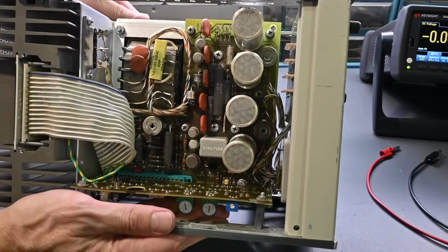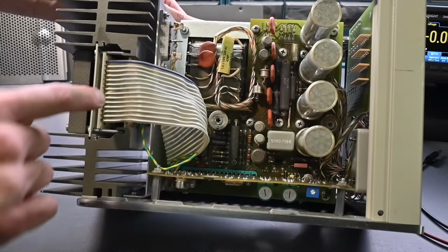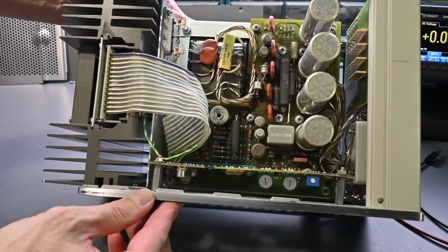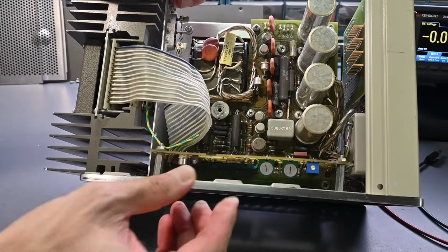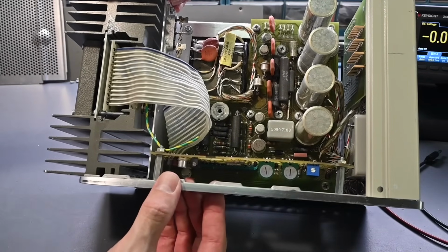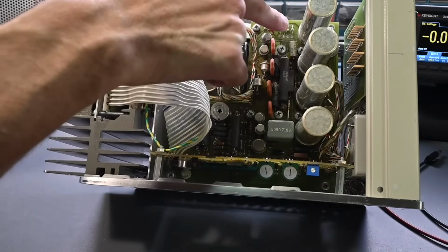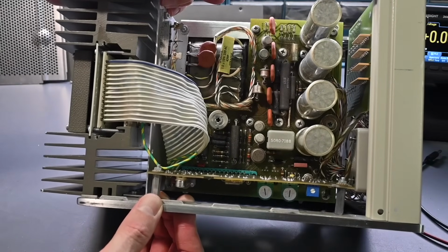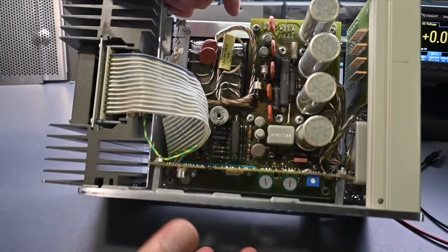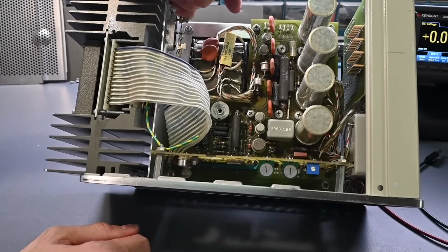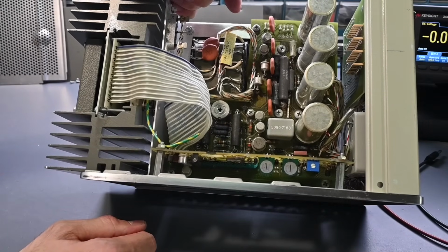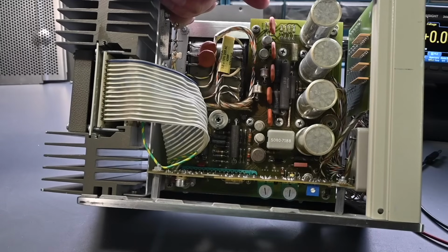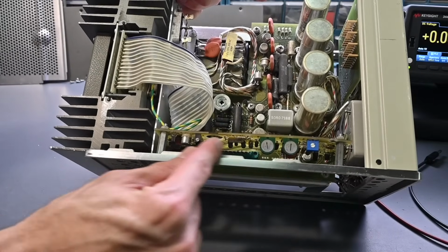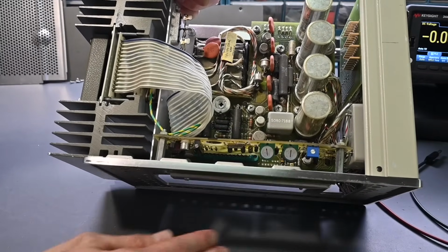Very large heat sink here on the back. Some power transistors I can see down there. Looks to be in good condition though. I don't see any components on this top side that are damaged or overheated. No evidence of leaking capacitors. So I'll go through and check these capacitors, make sure that they're in good working order. They're measuring okay. Now I've looked at the service manual already and looked over the schematic and have just kind of a general idea of where things are located. But this board right here is the main voltage reference board. Calibration potentiometers across the top edge right there.